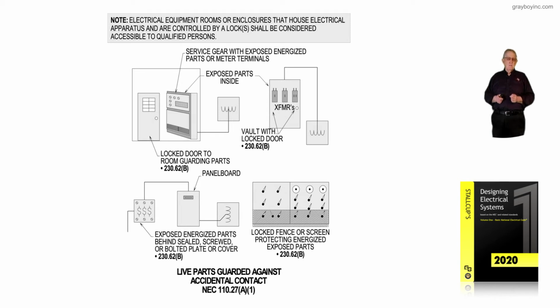And a lot of times inspectors require the lighting of that vault to be done in compliance with the National Electrical Safety Code, Table 111-1. It's in their ordinance to do that. And then notice the illustration to the left bottom. We have exposed energized parts behind a sealed, screwed, or bolted plate or cover. And just a regular screwdriver, maybe a special head type screwdriver, whatever, would guard those parts.